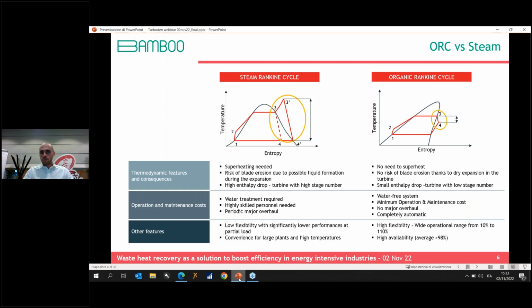The main difference, as highlighted in the graph, is about expansion — the segment represented as 3 to 4. You can see how in the organic Rankine cycle, this expansion always occurs in the dry vapor area of the diagram. This means the turbine always operates in dry conditions, no matter the inlet condition of the working fluid. This comes from the type of fluids used, which have a higher molecular weight compared to water, for example.